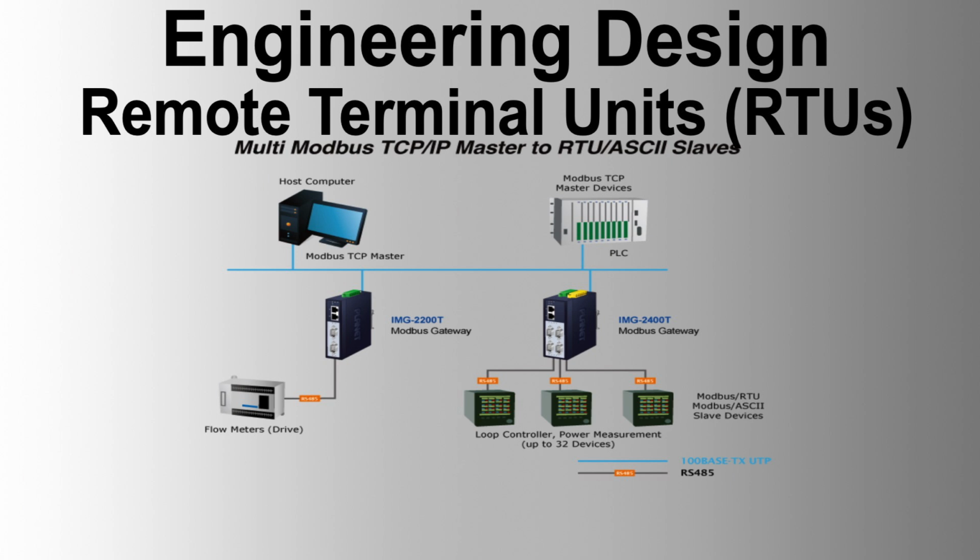Configuration: RTUs are self-contained units capable of collecting and processing data from intelligent devices through Ethernet and serial interfaces. They support integration with third-party systems via dry contacts, current or voltage signals, and contact-making pulsing devices. Key features include no false outputs during power-up or down, a minimum of 256 unique RTU addresses, selection interlock to prevent more than one control selection at a time, remote downloading of configurations and software, and remote diagnostic capabilities.